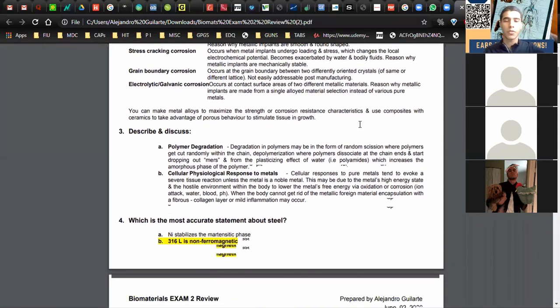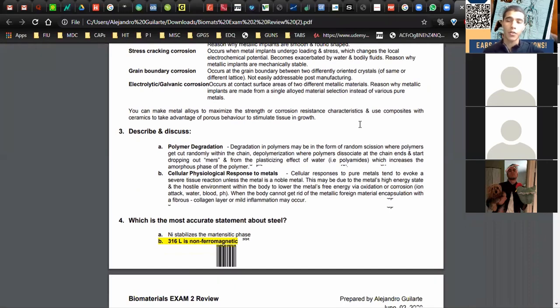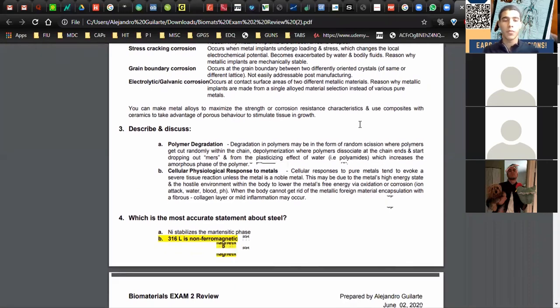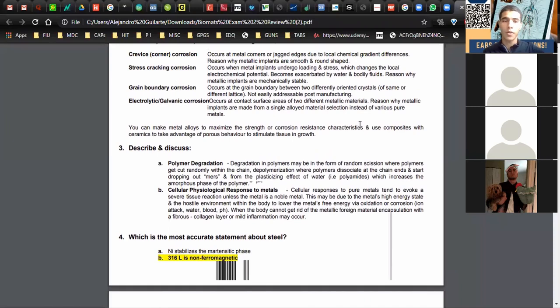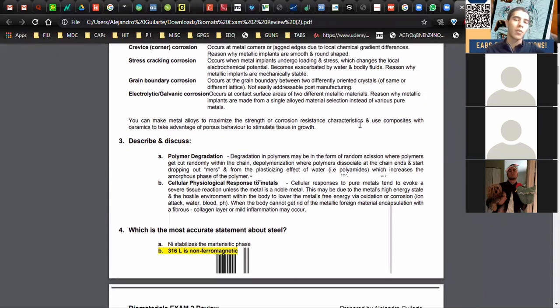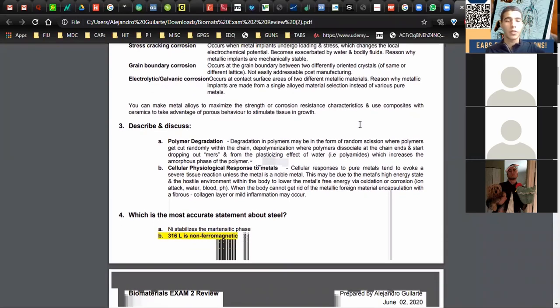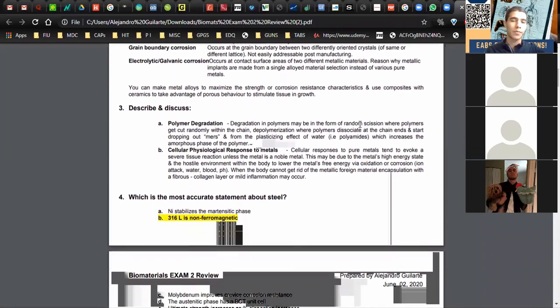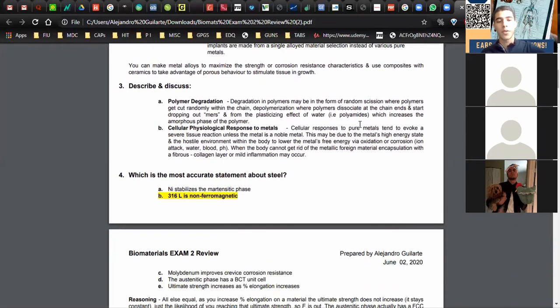Those are the biggest issues with metals and how you can address them as an engineer: make the device smooth, make it have fewer cracks, make sure it's mechanically stable to reduce crack propagation, and make it from the same alloy so different alloys won't create galvanic corrosion problems.